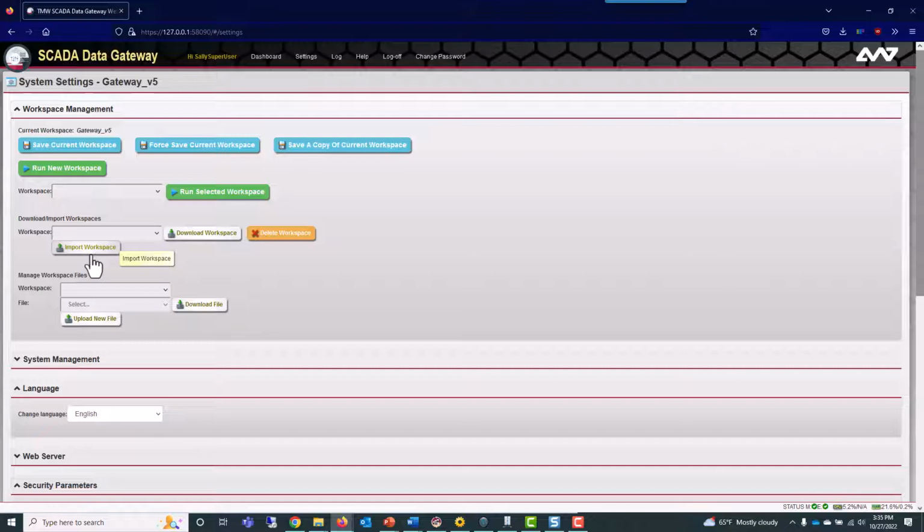So you can sit in a situation like I am right now, where I've got my SCADA Data Gateway, I'm trying to configure it all up, I have it in a testing environment with DTM being the SCADA master and all the downstream devices. I get it configured properly, I'm happy with how it's working, and then all of a sudden I can just sub out DTM with the actual physical devices and make sure things are still working properly. Then I can send that configuration out on site into the system that's actually been deployed and verify everything still works properly there too.